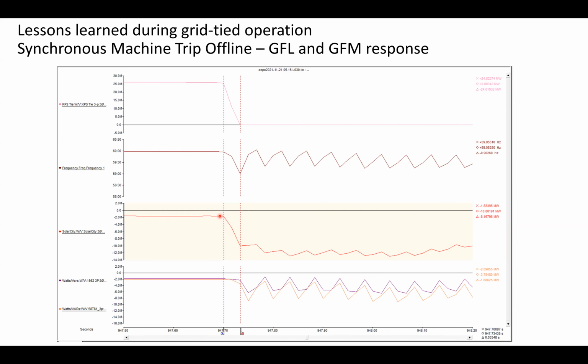we look at negative power as power from the IBR to the grid. So as this IBR is pushing out its peak power, because of that delay in the grid following, it's actually pushing out its max peak power here. By that time, the grid forming inverter is pulling back because frequency has recovered. Now you're getting the seesaw between the grid following and grid forming, going back and forth. Even if you look at a spike here, you have a minimum real power spike from our grid following inverters, but a peak in our grid forming inverter, and they just start fighting each other the whole way. And that's affecting our system frequency.